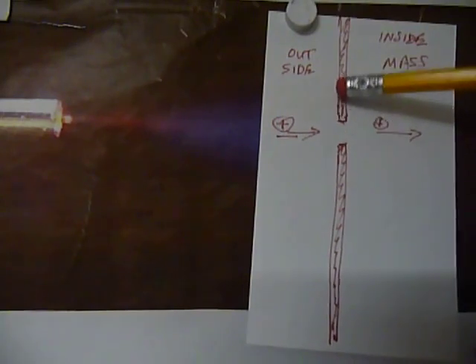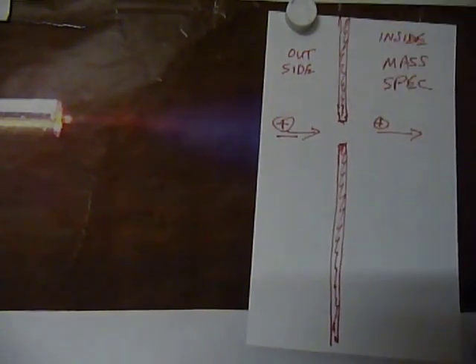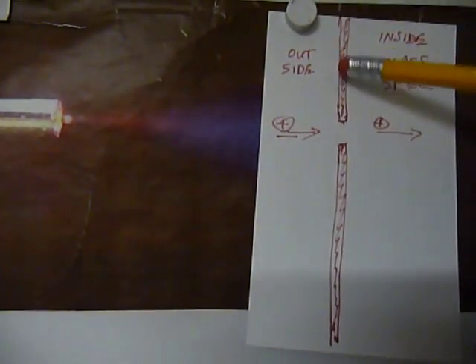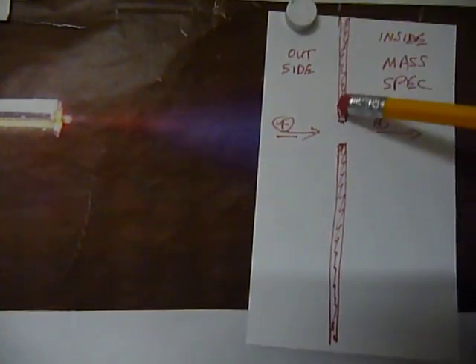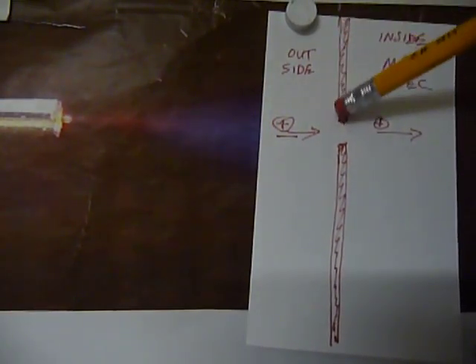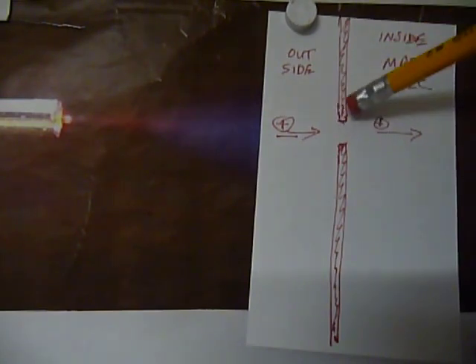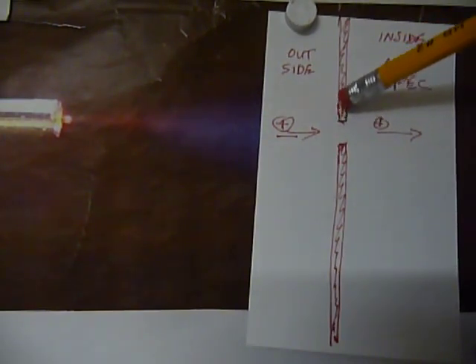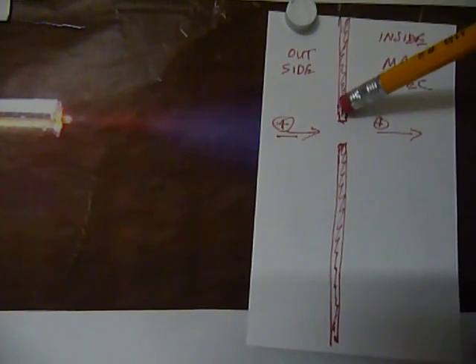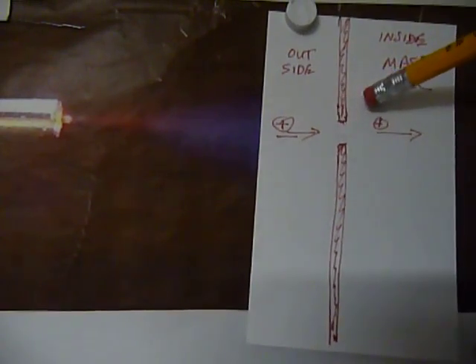And this charge, some companies call it skimmer voltage, some call it orifice potential. It also helps break up solvent clusters. And so, in the exactive situation, we had it going from 24 volts to 50 volts.